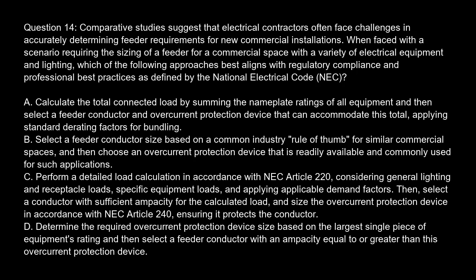Option C. Perform a detailed load calculation in accordance with NEC Article 220, considering general lighting and receptacle loads, specific equipment loads, and applying applicable demand factors. Then, select a conductor with sufficient ampacity for the calculated load, and size the overcurrent protection device in accordance with NEC Article 240, ensuring it protects the conductor. Option D. Determine the required overcurrent protection device size based on the largest single piece of equipment's rating, and then select a feeder conductor with an ampacity equal to or greater than this overcurrent protection device.